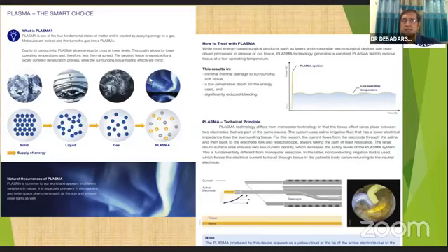That's the reason for the less thermal spread. Most of the time when we use either laser or monopolar, it is mostly a thermal-driven process to cut or remove the tissue. But here it generally has a constant field to remove the tissue. By this, it causes minimal thermal damage to the surrounding soft tissue. The plasma kinetic has a very nice yellow cloud at the tip of the electrode. It's all because of the sodium inside the medium.